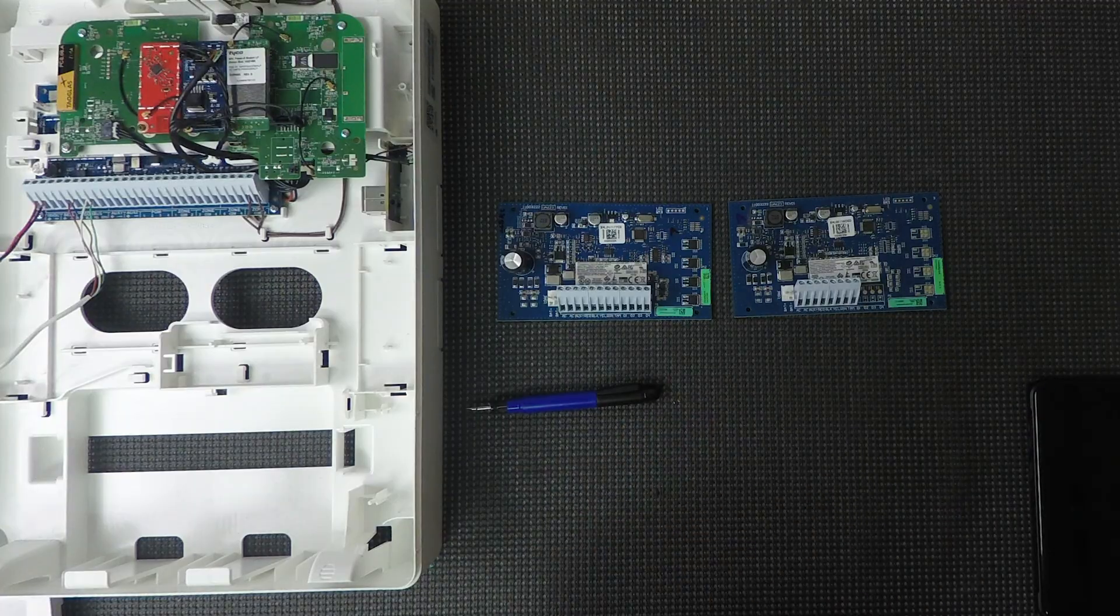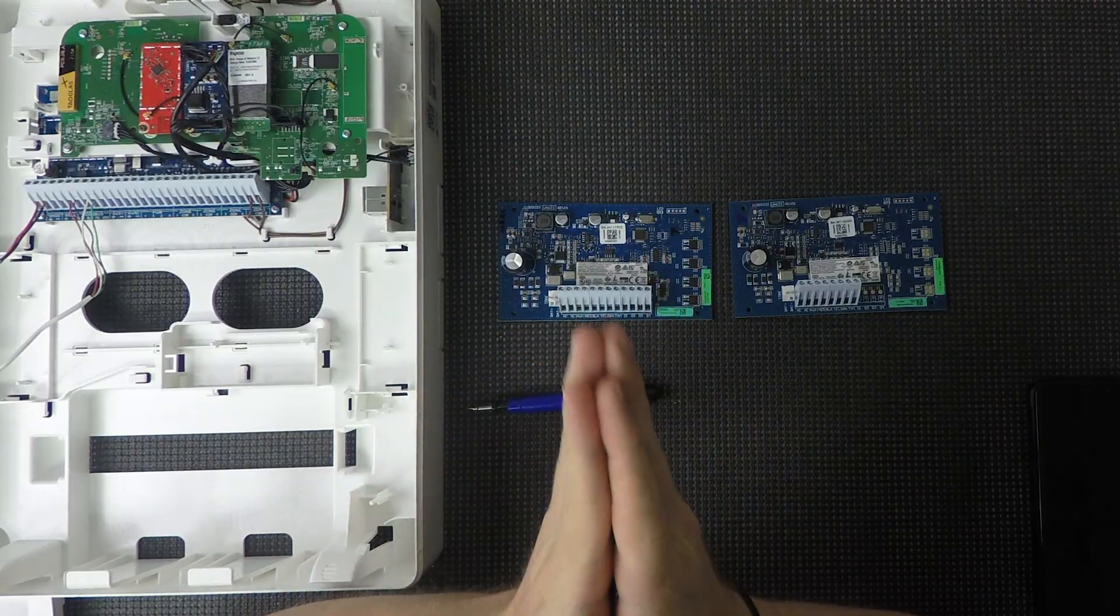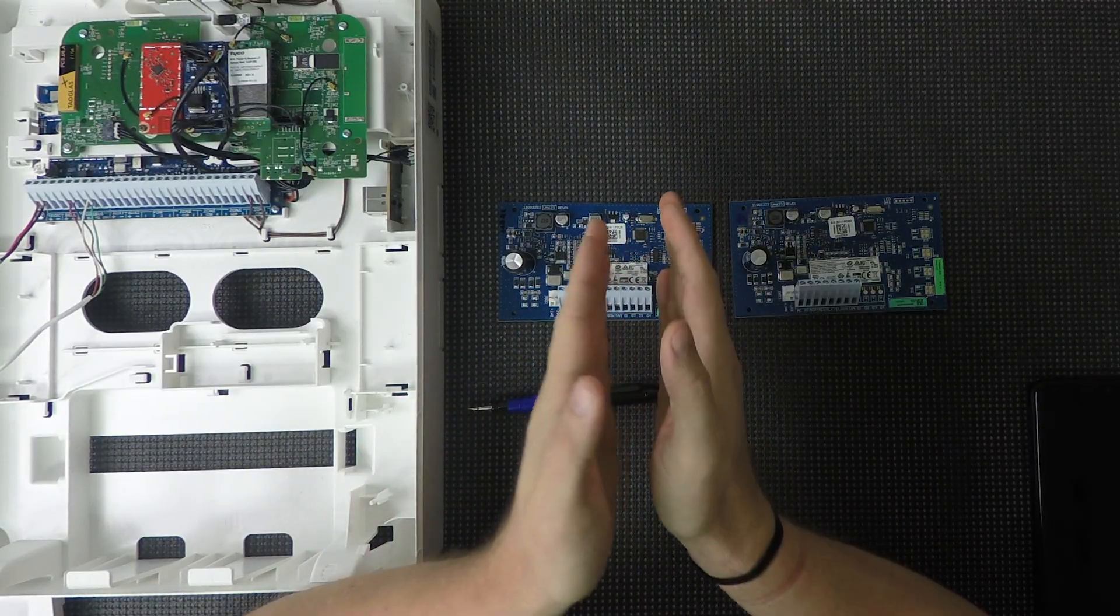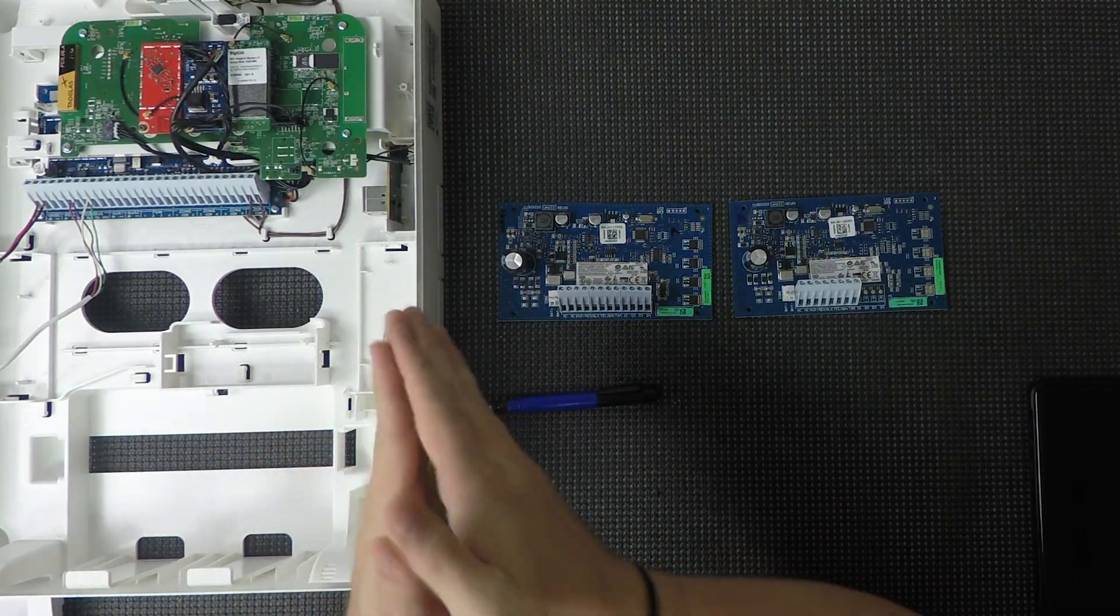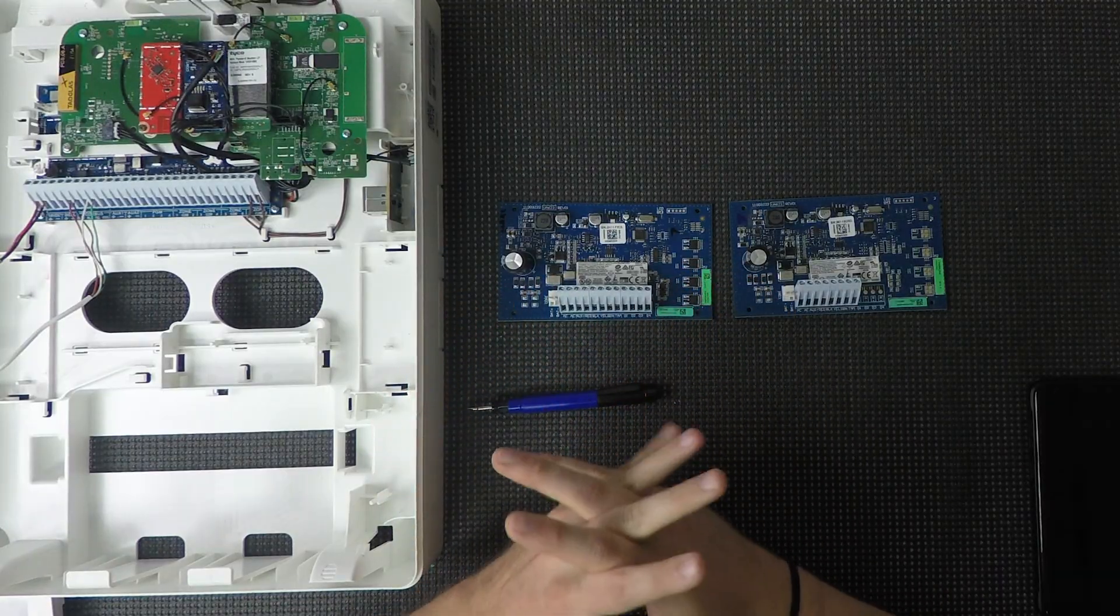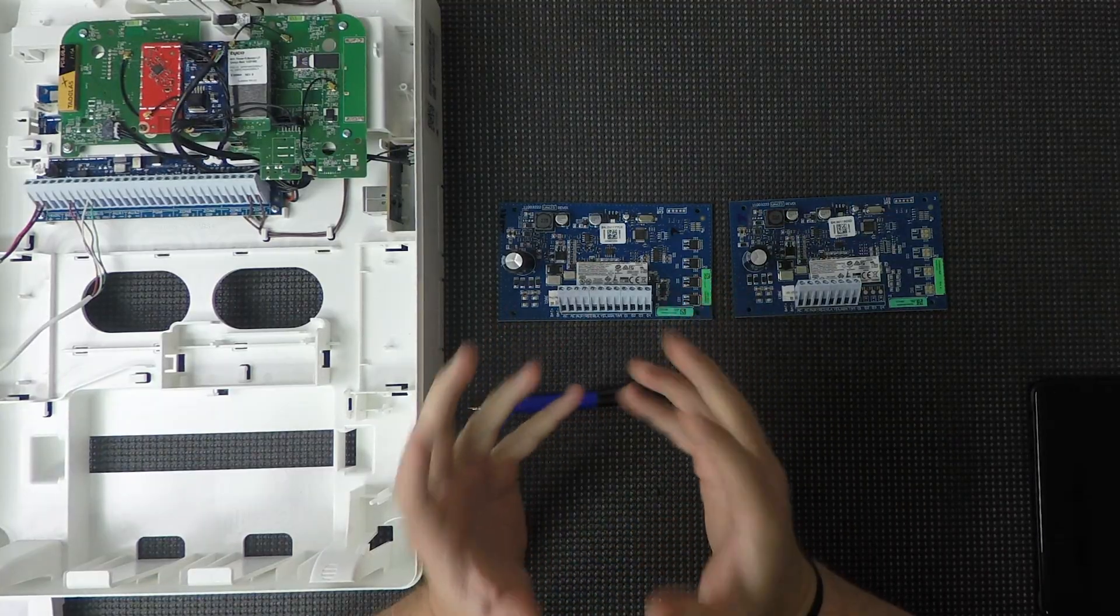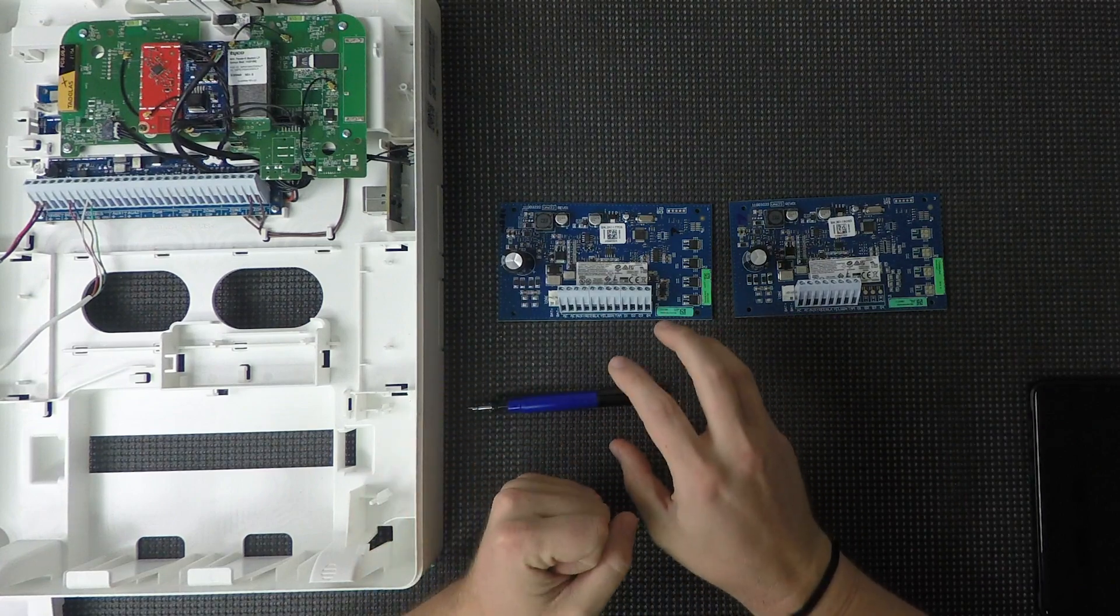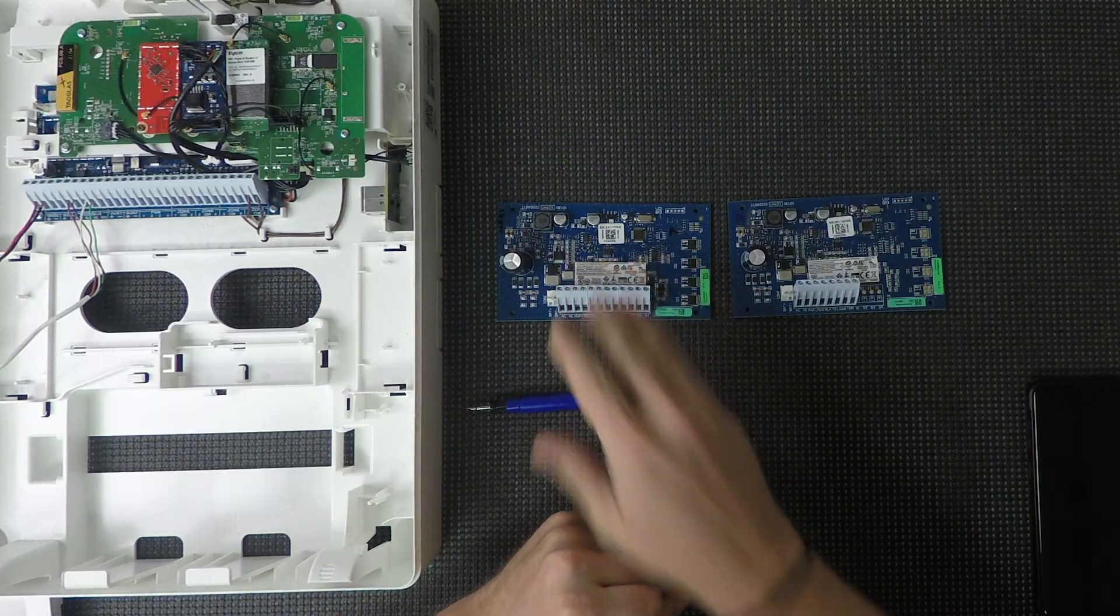So both of these modules offer up to an amp of additional power for your alarm system. Now to clarify, what that means is they don't add an amp of power to the available power of your system. They basically have their own separate amps worth of power supply. So anytime you're hooking one of these up, you do need to plan to have all the wiring for the devices that will be powered by your power supply be run to the location of the power supply.